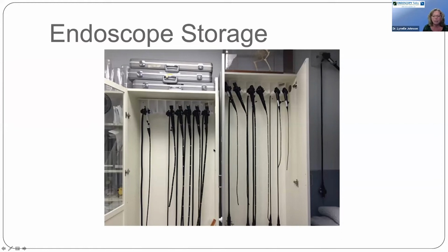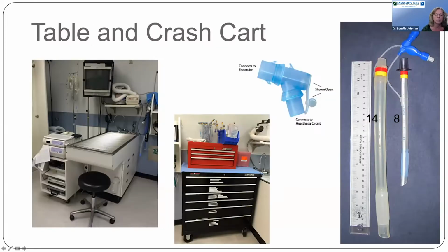For those of you that have a lot of endoscopes or you use your endoscopes frequently, you know that proper handling and storage is critical for avoiding any damage to the endoscopes and also maintaining them in as clean a condition as possible. So our endoscopes are cleaned using a glutaraldehyde-based product, and then they're air dried in our cleaning room and then hung up for storage. We have a large endoscope that we use for after hours endoscopy, and then most of our standard bronchoscopes are in this closet. One of the important things I'll point out is you want to keep all of your endoscopes away from any of the hinges because they can get trapped in there and broken. Our smaller endoscopes, so those under 3 millimeter outer diameter, are generally stored in their containers above the endoscopy storage.